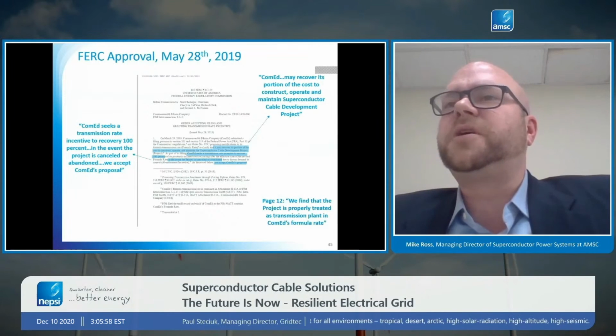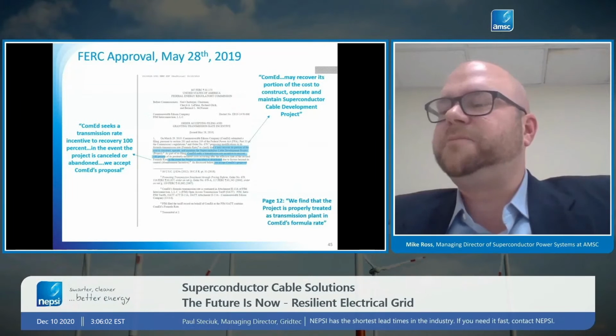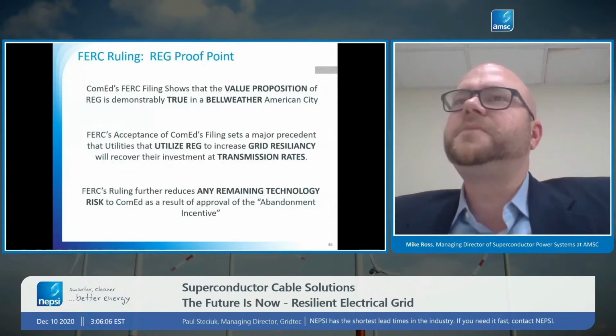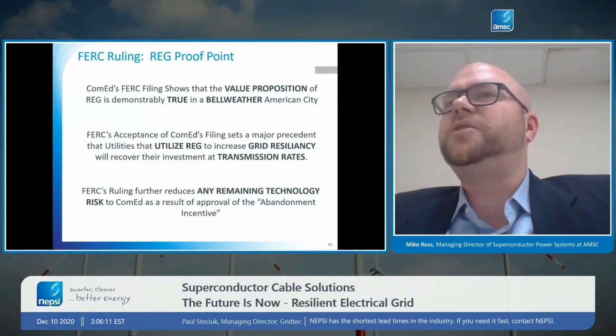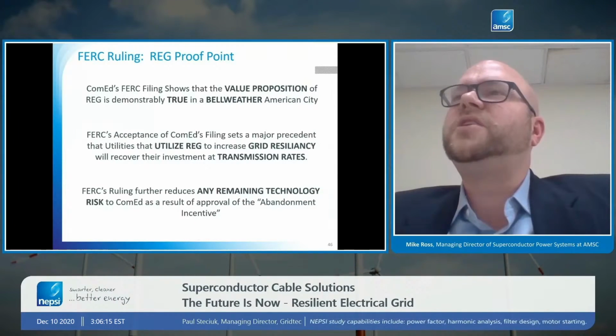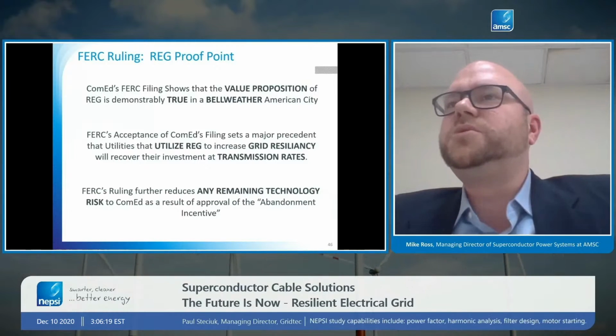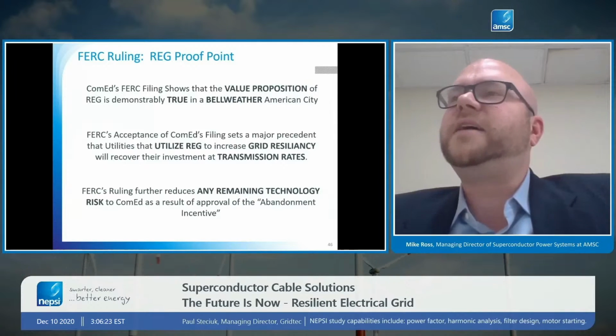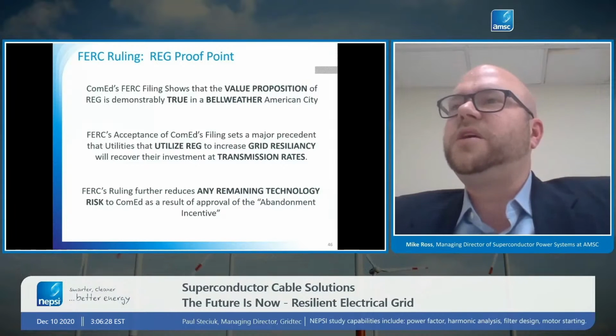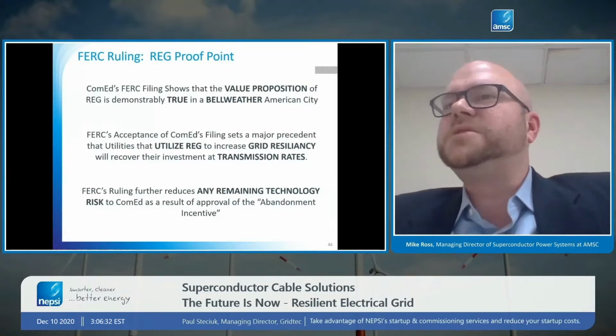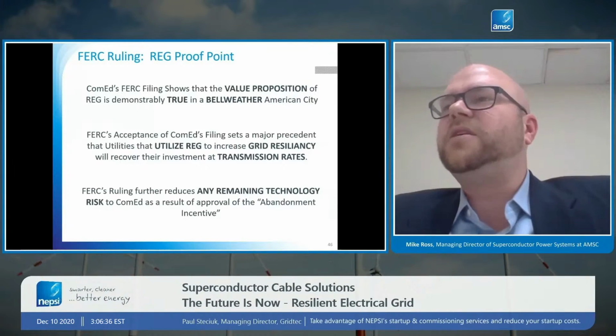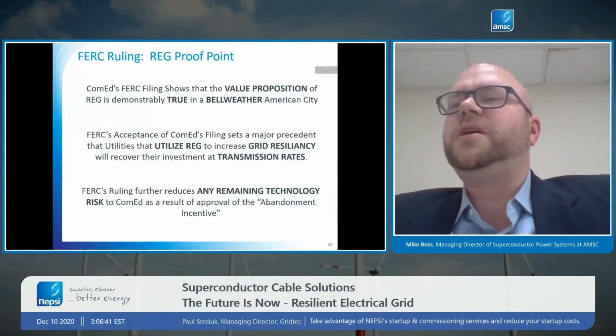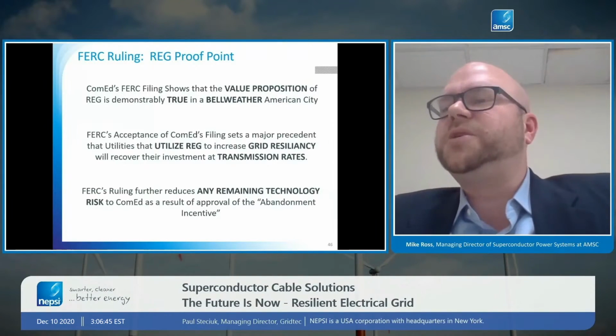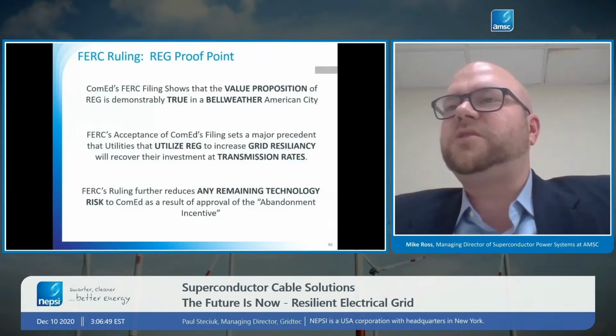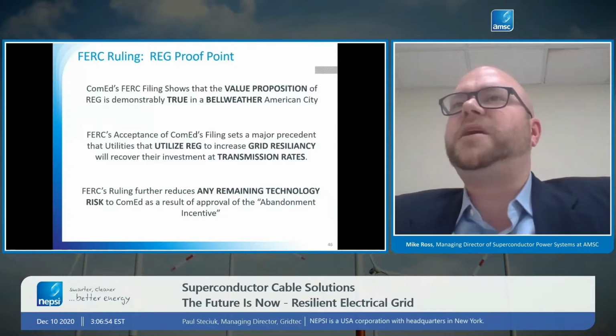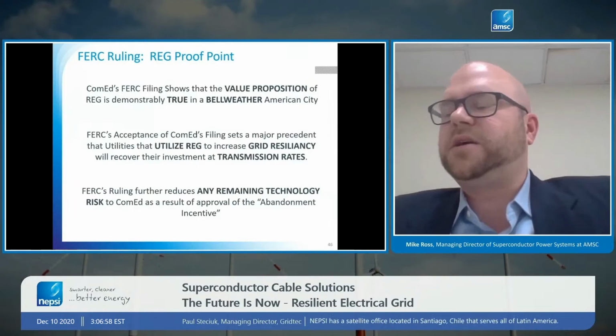So what that means is that superconductor cables are now a proven and accepted technology for utility applications. That's the result of a utility in a bellwether American city that has shown that the value proposition I talked to you about today is true. That the precedent of this filing shows that superconductor cables and resilient electric grids can be used for grid resiliency, and that resiliency can be recovered as transmission assets. And another aspect of that filing had to do with risk management. Because FERC approved the project, the technology risk, or anything that people might be concerned about regarding the newness of this technology, is shifted off of the utility because of this approval. So the technical risk has been retired on the technology from the utility's perspective.